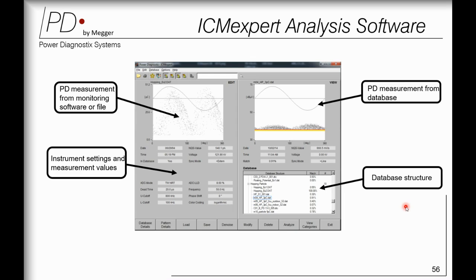That means, let's say I'm a new user of a PD instrument and I'm not an expert in it. So we have a built-in library in the software where different types of PD patterns have been captured, like voids, surface discharge, floating particles and all. All those things are stored in the library. So let's say when I have done some measurement on the GIS, I'll just click on load. My pattern will be loaded in the software, with the details of what was captured during measurement. I will just click analyze, and it will compare with the PRPD pattern library, and it will give you an indication of what type of PD source you have in your electrical asset. Is it a void, surface discharge, or anything else.